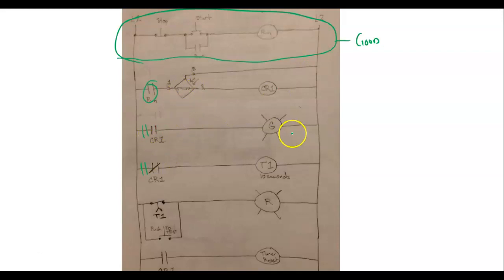So that looks good - car comes in, energizes this. The problem we have is this is true all the time, so that means this is closed, green light's on, timer's off. We probably need one more contact down here on the red light, we probably need a CR contact down in here, and you don't have to put this, guys, because that comes from where?